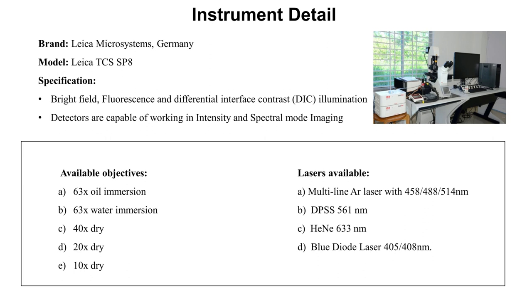The confocal microscope at CSR NIST is from Leica Microsystems, Germany. The model number is TCS SP8. It has many specifications including bright field, fluorescence and differential interference contrast (DIC) illumination, with a confocal scan head attachment. Detectors are capable of working in intensity and spectral mode imaging, and it is capable of simultaneous detection and separation of a minimum of 5 fluorophores. Five different types of objectives are available, including dry, oil immersion, and water immersion.